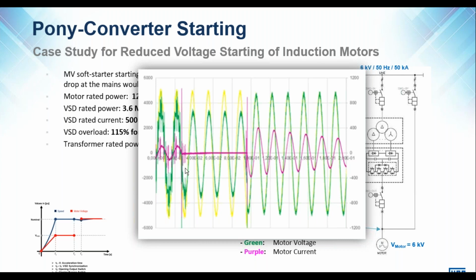Then after some time, we want to close the bypass switch. We first need to open the output, the VSD output. The motor maintains some voltage even though the VSD is switched off in this time frame. And after some time, at this point where there's a small current spike, that is when we close the bypass switchgear. So we do get a small current spike because our motor voltage is sitting at approximately 4 kV and our supply voltage is 6 kV.